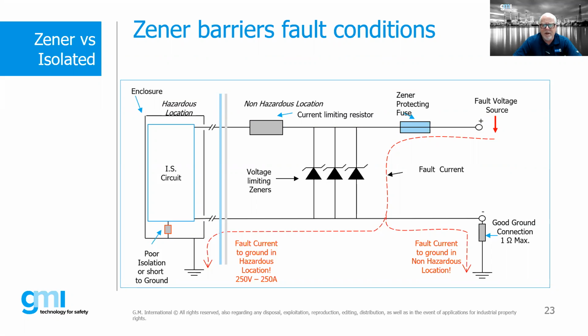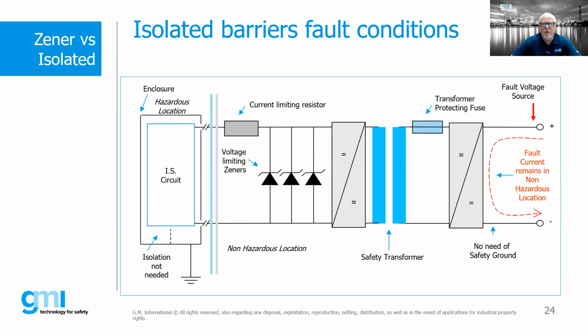So this is something that actually can happen, but we have to make sure that our good ground, if you will, is separate from our normal dirty earth. So it's very important that we don't have some sort of fault condition coming back from earth via the loop into the hazardous area. So this is what happens under a fault condition with Zener diodes. And again, going back to a galvanically isolated product, our fault condition stays within the non-hazardous area because of the use of the safety transformer. So that's really the main difference between a galvanically isolated and a Zener diode type product.